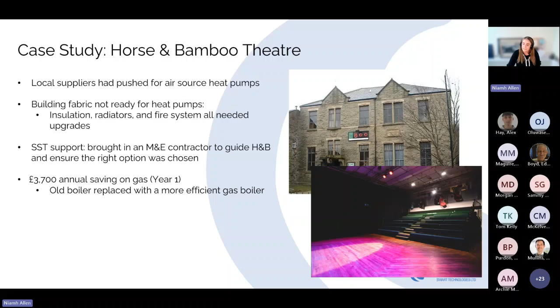They came to us, and we were doing monitoring, so we had all the data for the building, how it was occupied and how it ran in terms of energy. They said, I don't think this is right, is an air source heat pump right for our building? So we brought in our own M&E contractor, and very quickly they said no, it will need new insulation, new radiators, new pipe work, and a new fire system. So we worked with that contractor to replace what was a very old boiler. We moved them to a more energy efficient gas boiler and saved them nearly £4,000 in year one. So for them, that was the right sustainability approach, and I think sometimes it's easy to go with what's new and exciting, but is it right for the particular building?